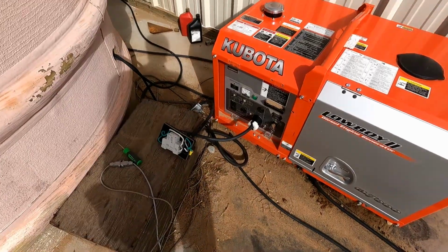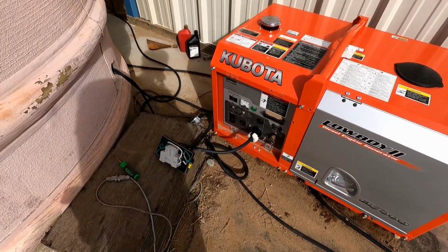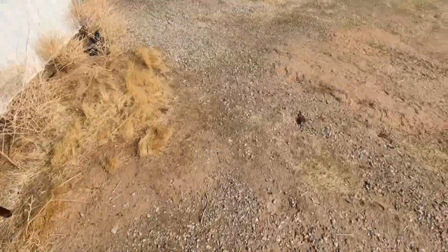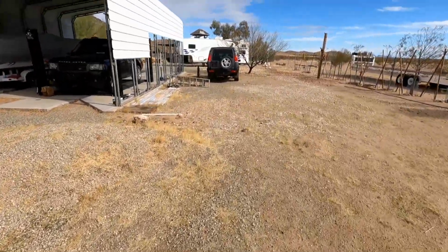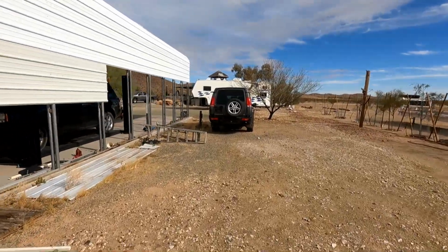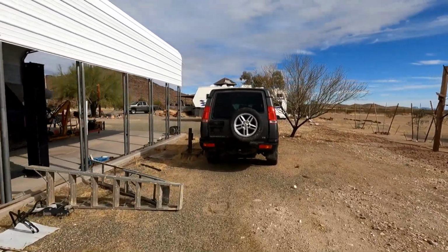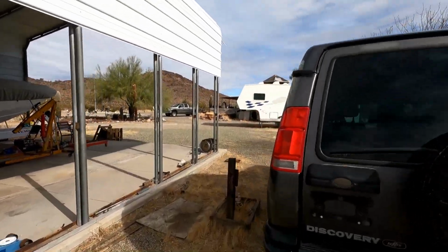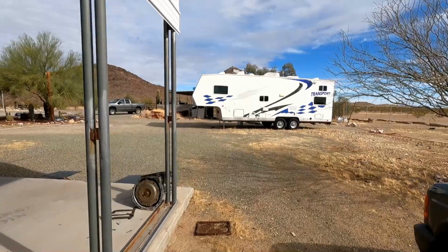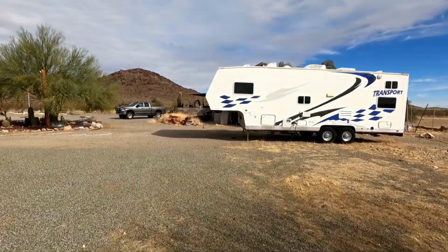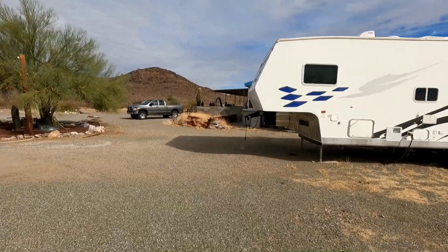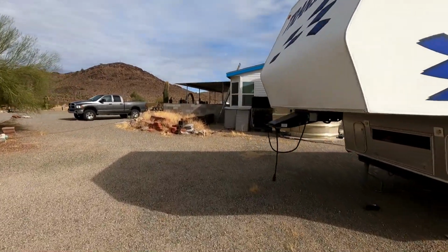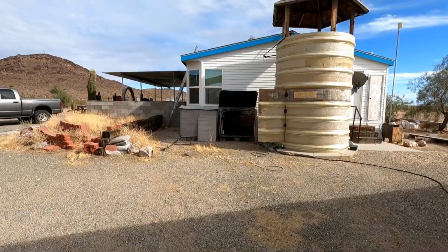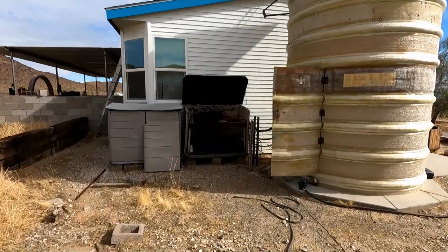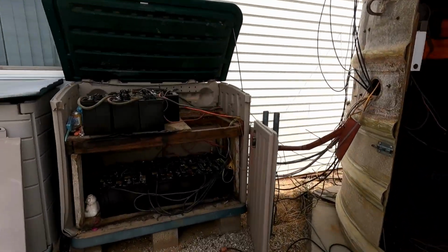So that takes care of all the surge protection issues. And the final issue, we go back 100 feet back to the solar power setup, will have to do with the auto start of the generator. We're going to be doing a whiteboard session shortly here to further explain schematically a lot of these technical details. But a lot of this does revolve around the fact that remote generator is automatically controlled. And automatic generator starts have some certain considerations that we're going to talk about.